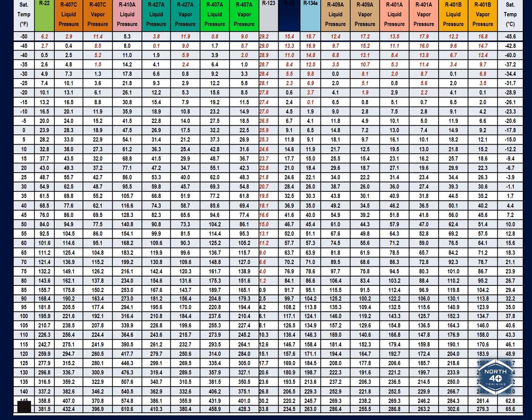So you would not be able to go off that temperature chart that's in the middle of those dial style gauges if it corresponds with 410A. So if we've got 60 psi, but we're working with R22 on 410A gauges, we can utilize the pressure on the R410A gauge. Say we're working with 60 psi. Now go to the R22 across the top of this PT chart, and the R22 at 60 psi is operating at, if you look just to the left of that, 35 degrees. Okay, so 35 degrees would be much more reasonable.